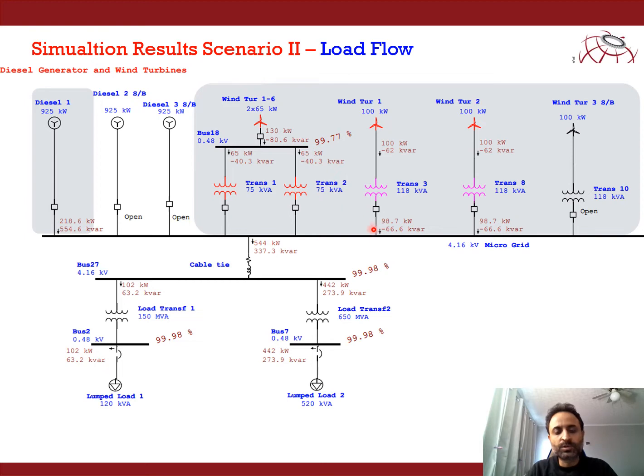One more observation that we can make from this load flow study is that the reactive power generation from the diesel generator has increased. This is expected because wind turbines are induction generators, and for running they need reactive power. As a result, you can see the minus reactive power sign here, which is the reactive power consumed by the wind turbines and is generated by the diesel generator. But overall, the active power has reduced, and as a result, the fuel cost and the emission of the diesel generator will reduce, and we will have renewable energy generation from the wind turbines. At the load end, we can see that the voltage is still within limits, higher than 95%. So we are able to achieve 99.98% voltage on the buses.